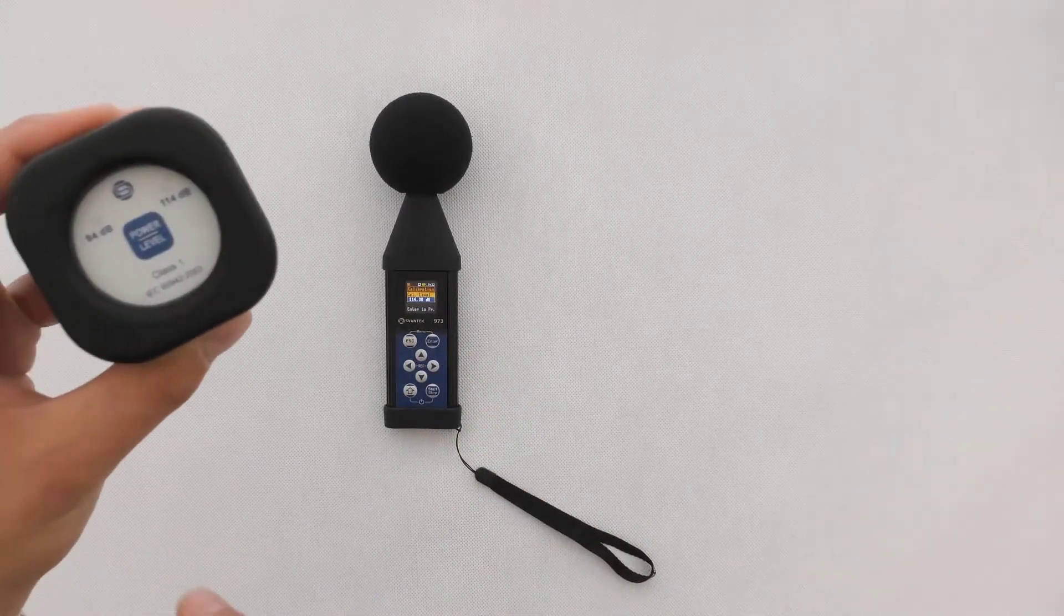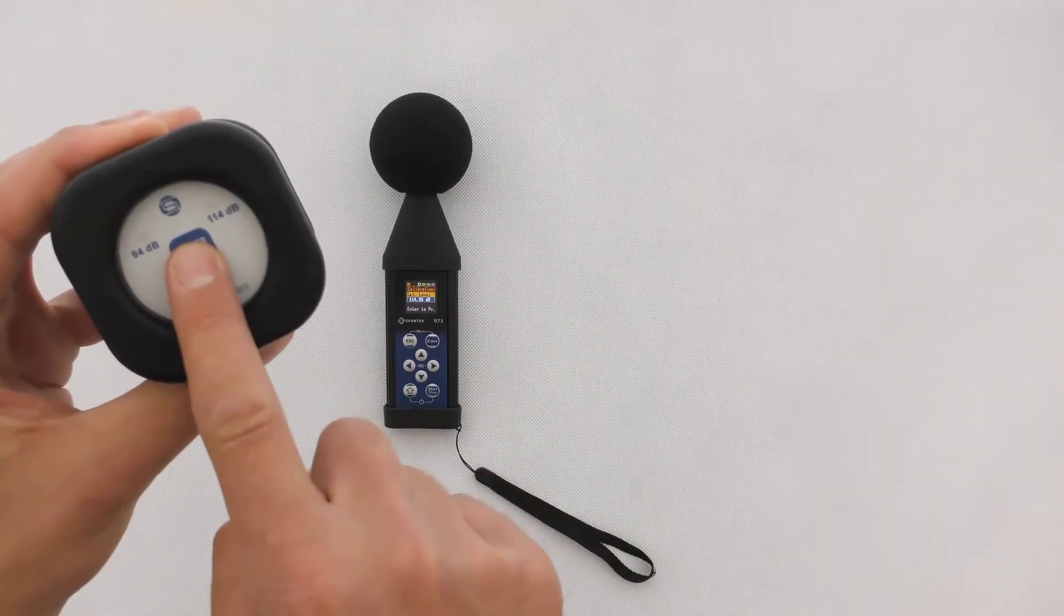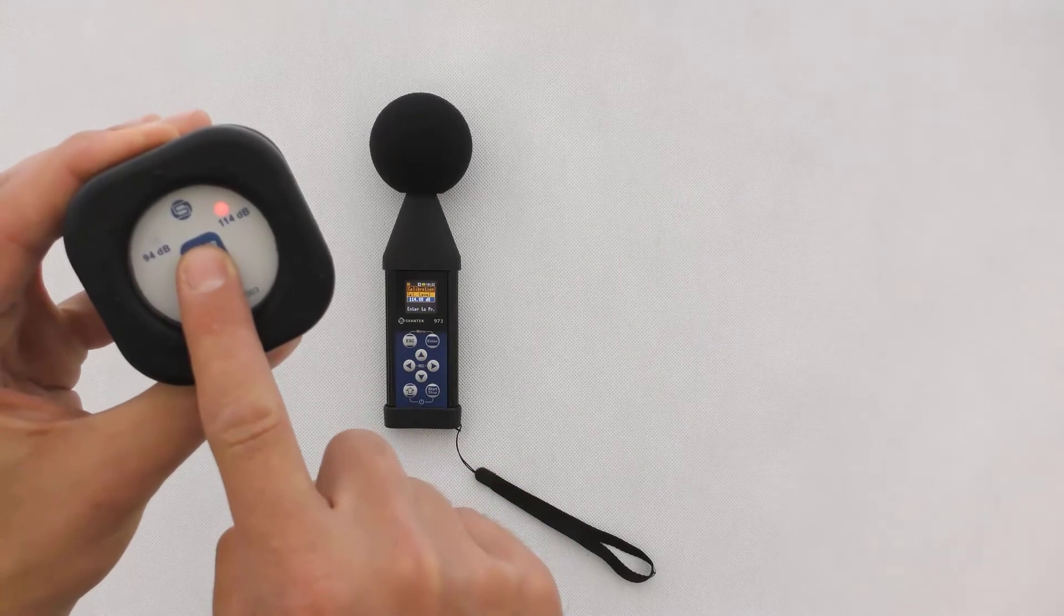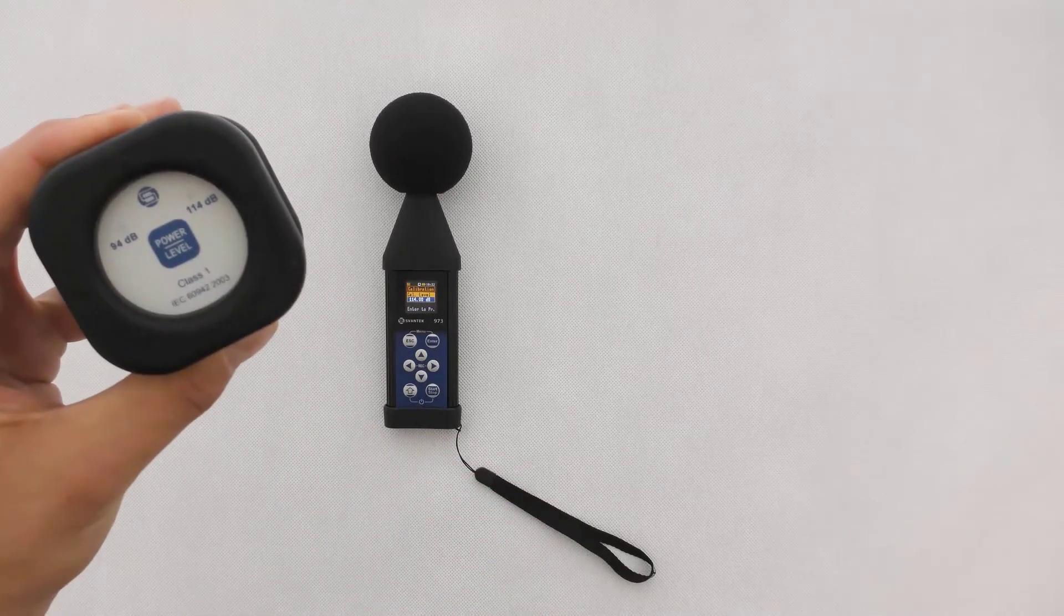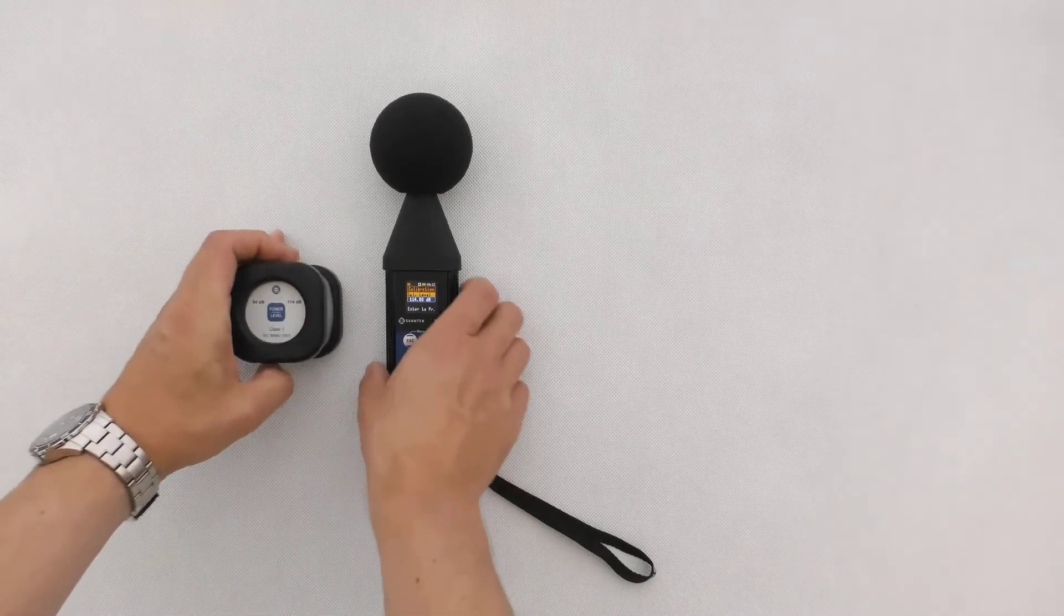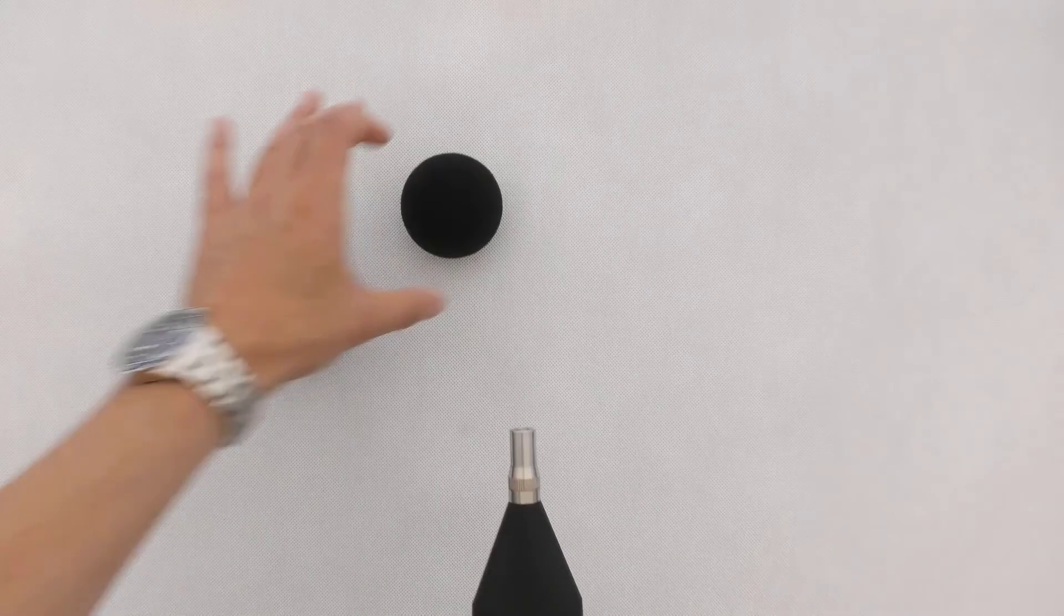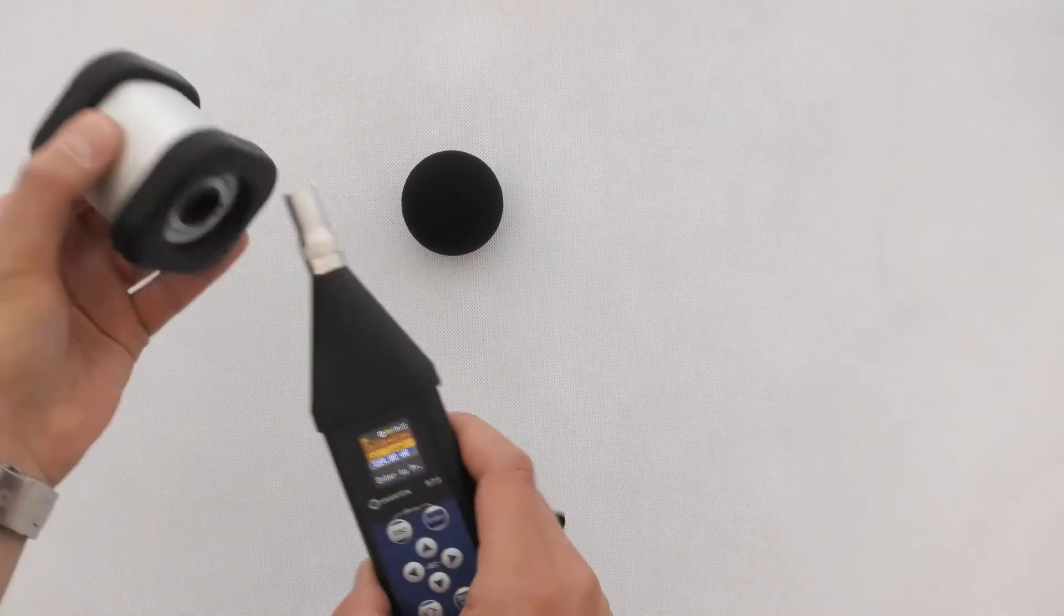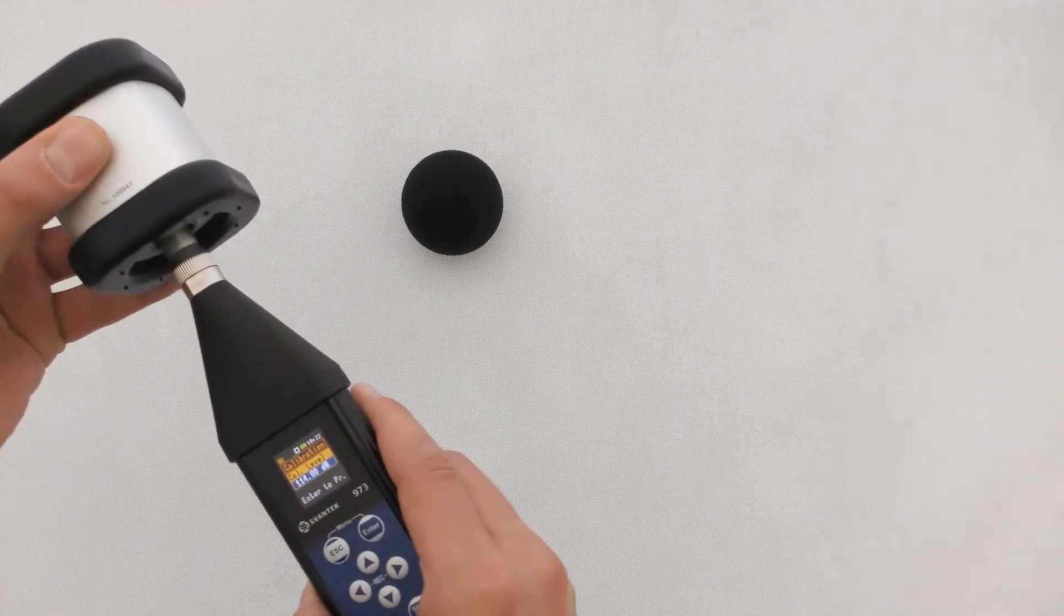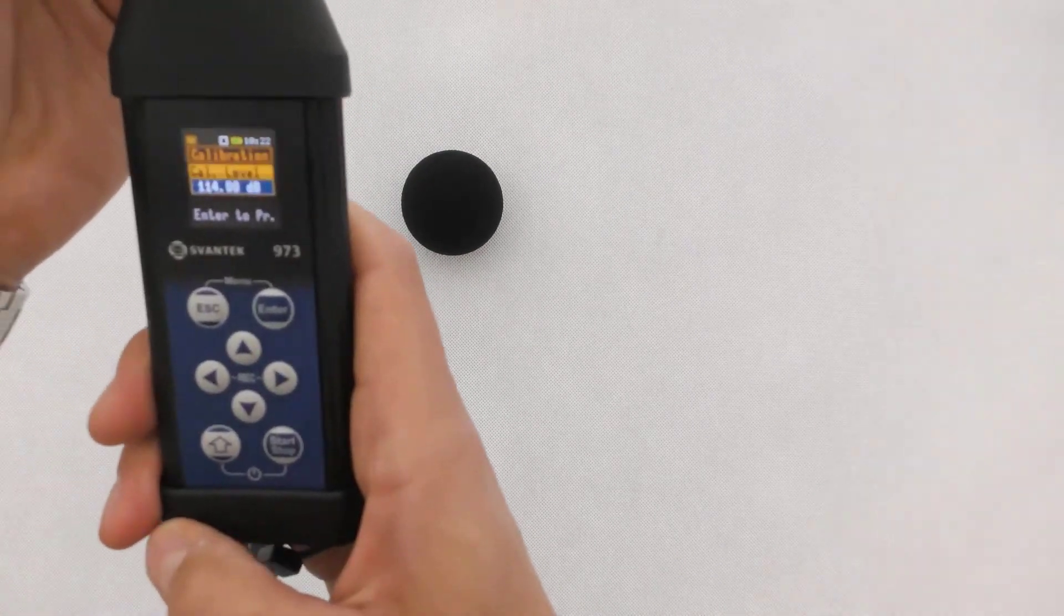Switch on the calibrator, set it to 114 dB at 1 kHz, and carefully insert the instrument's microphone inside the Svantek sound calibrator.